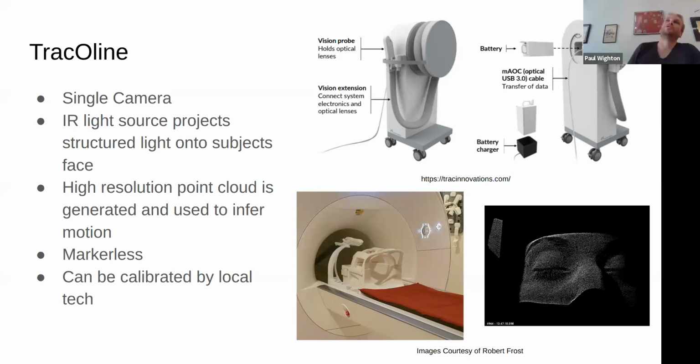This might be a situation where navigators are a good fit. Even if you didn't want to do reacquisition, or prospectively correct, you could run a navigated sequence and at least quantify motion. And you can do that without any external hardware or calibration. Can that be done a week after acquisition? I guess without k-space, maybe we can't, right?